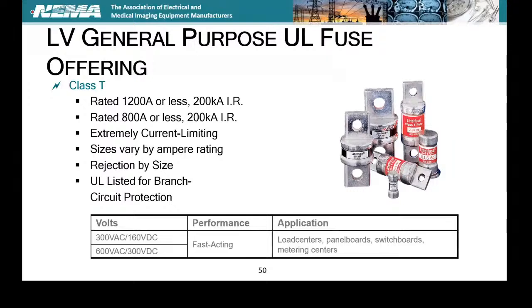There's a lot of bang for your buck in here because they go up to 1,200 amps, but you can put a smaller enclosure. You'll see Class T's in service entrance equipment type of solutions, in panel boards or metering centers. There you go, metering centers. That's your service entrance stuff. Very popular in the service entrance area.